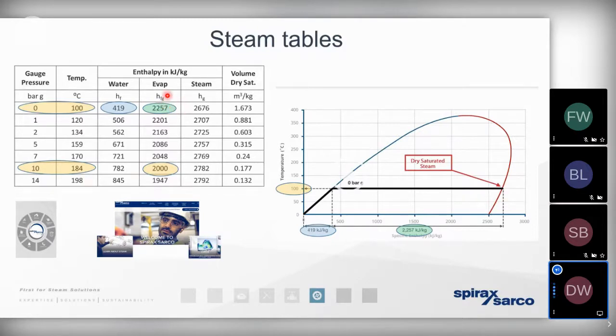And what you'll also see is the opposite is true with the sensible heat, or the enthalpy in the water, the energy that's present in the condensate. If we reduce the steam pressure, we've increased the energy that can be used by the process, and we've reduced the energy that is present in the condensate. Remember, that condensate doesn't have any value to us. So that means as that sensible heat passes across a steam trap and sees a fall in pressure, there's going to be far, far less flash steam being produced.